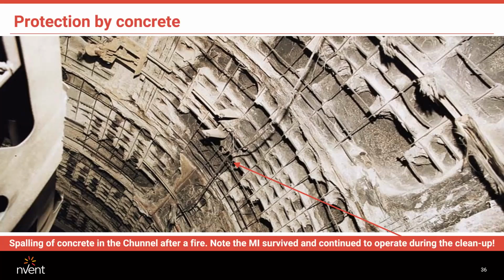And the heat got so intense, you can see chunks of concrete just fell away, because concrete contains moisture. When moisture is exposed to heat, the moisture expands and the concrete just starts to fall away, otherwise known as spalling. The MI cable withstood that intense heat, powered the emergency lighting, and even operated in the aftermath when they went in to clean up the tunnel. So that's an interesting slide, and it shows just how robust and durable MI cable is.